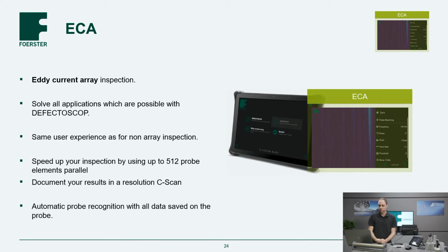And the documentation will be possible with a high-resolution C-scan, so it's very nice to save the whole eddy current signal as an image. And for sure, the probes have a chip on them, and all probe data are saved on this chip. So everything which is more complicated is set up completely in the background.